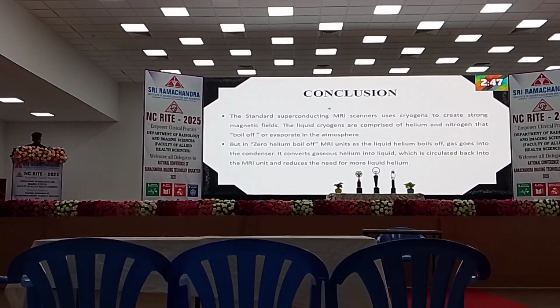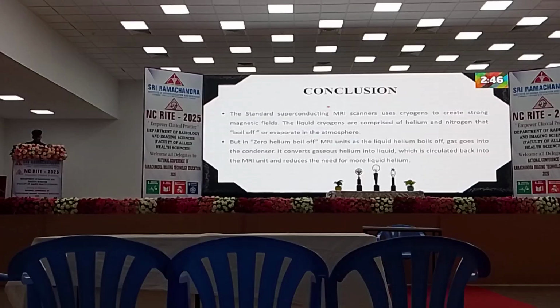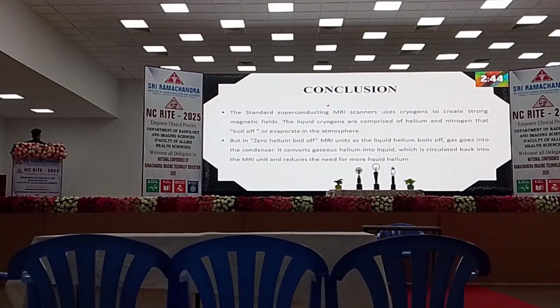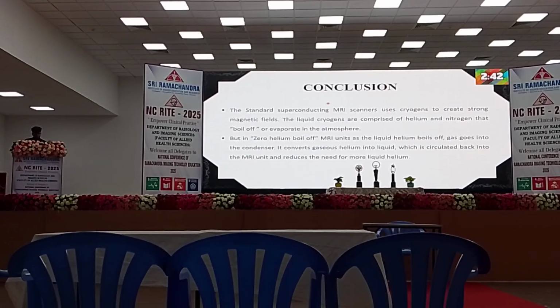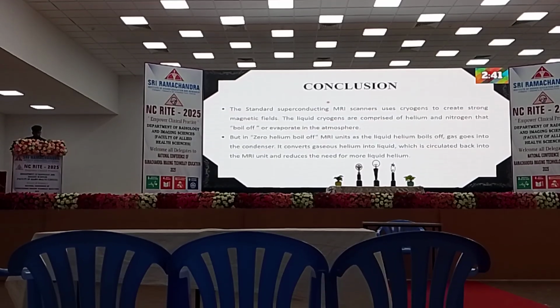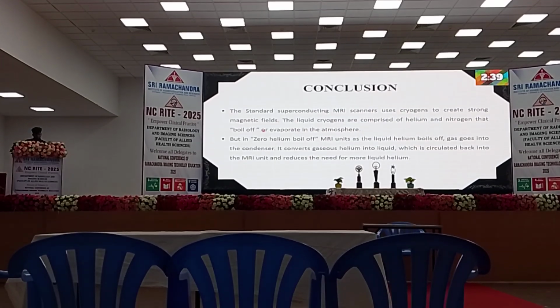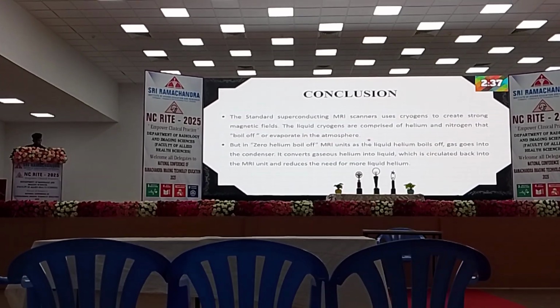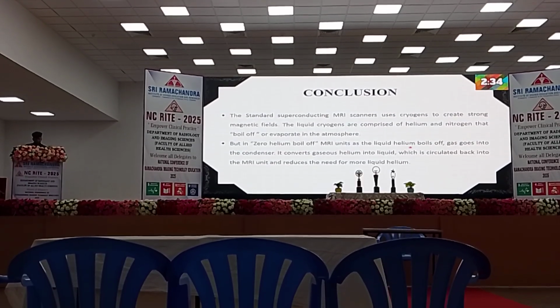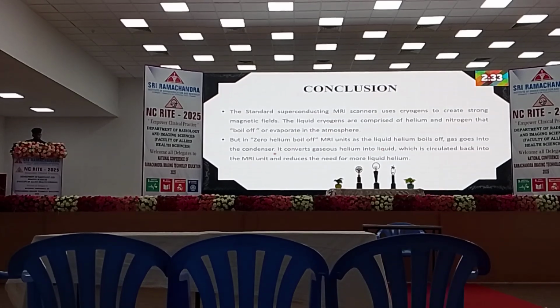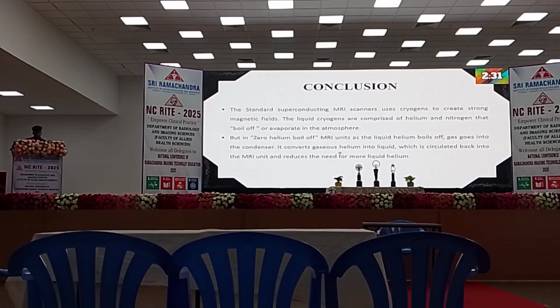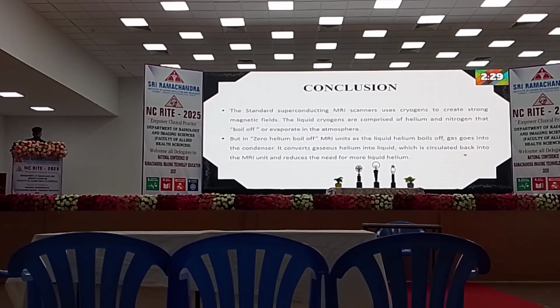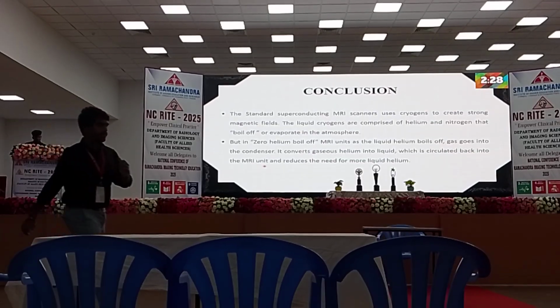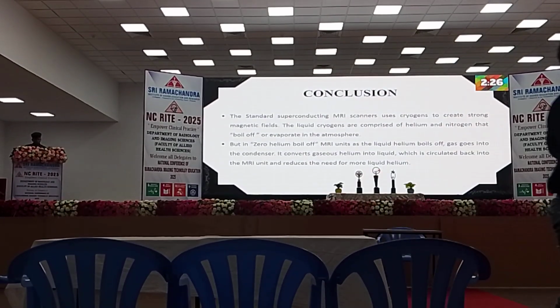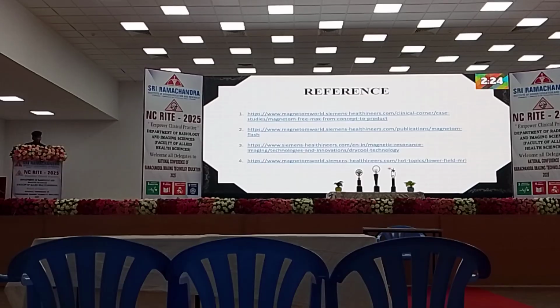In conclusion, a standard superconducting MRI scanner uses cryogens to create a strong magnetic field. Liquid cryogens comprise helium and nitrogen that boil off or evaporate into the atmosphere. But in zero helium boil-off MRI units, the boiled-off helium gas goes into the condenser. It converts gaseous helium into liquid which is circulated back into the cryogenic system and reduces the need for more liquid helium. These are my references.